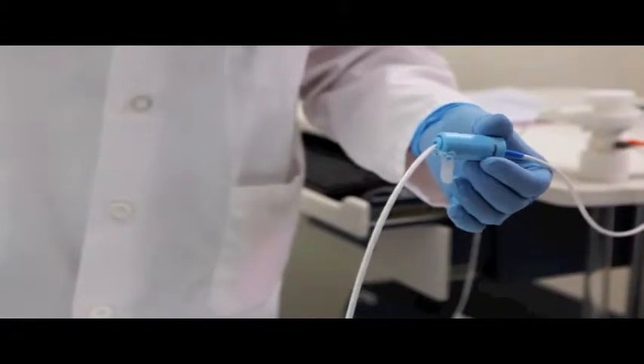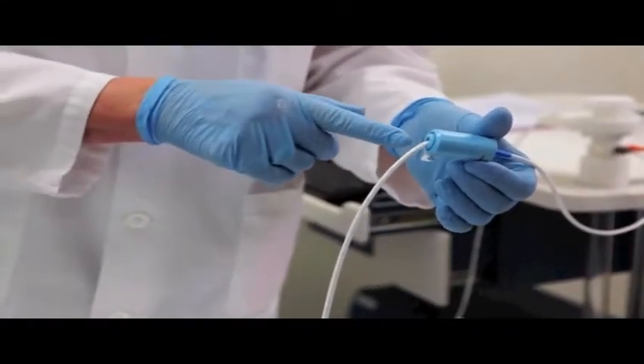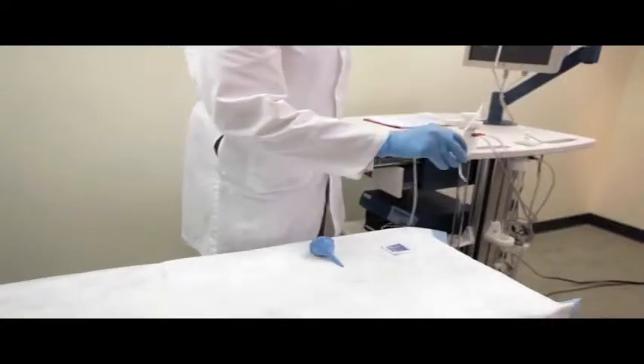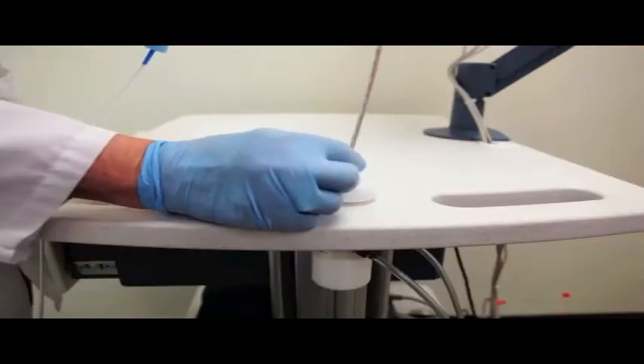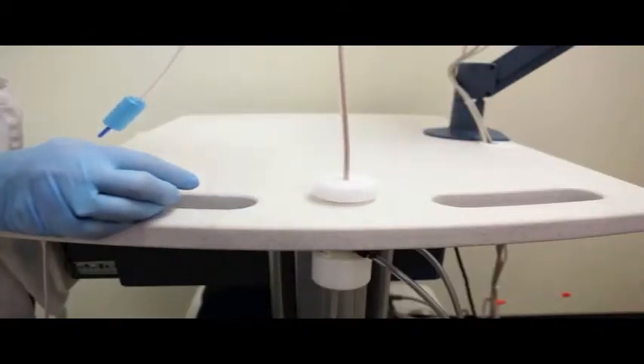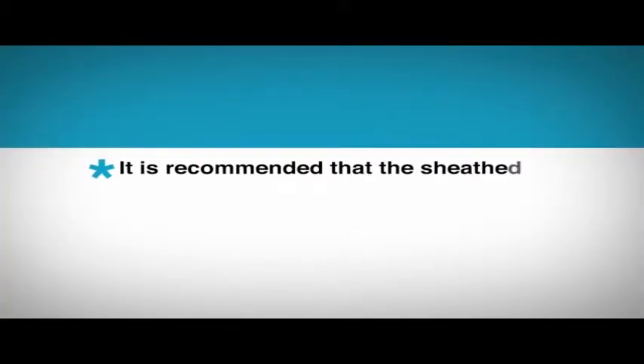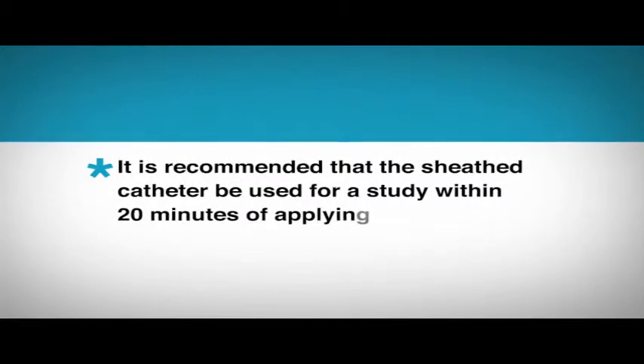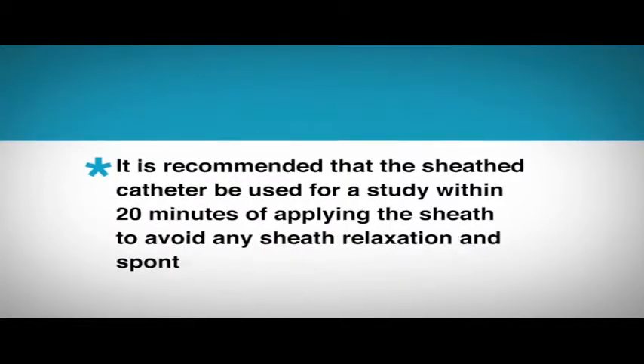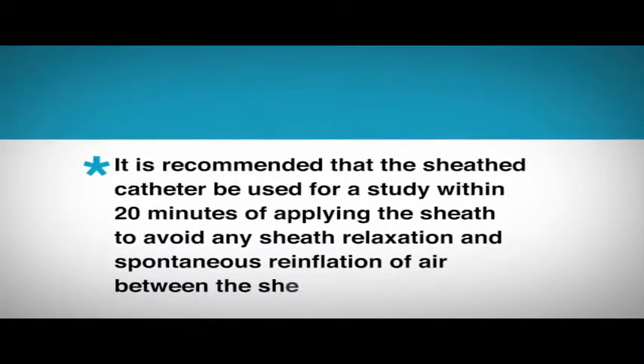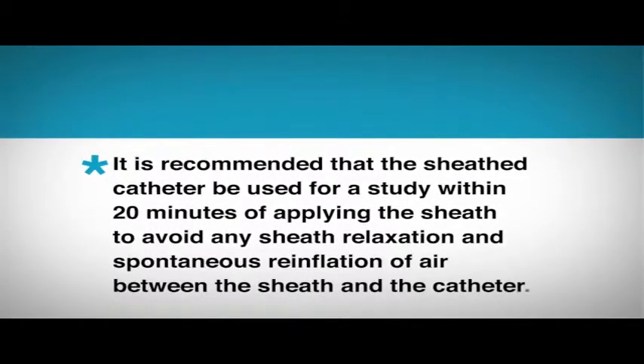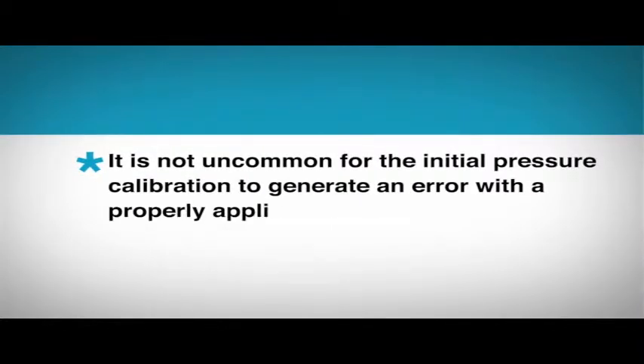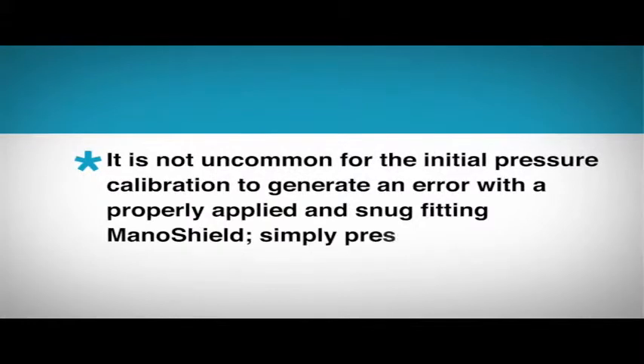If the tab is not secured against the base of the slider, it may cause the catheter to bend. You are now ready to pressure calibrate the catheter and then intubate the patient and perform the procedure. It is recommended the sheathed catheter be used for a study within 20 minutes of applying the sheath to avoid any sheath relaxation and spontaneous reinflation of air between the sheath and the catheter. It is not uncommon for the initial pressure calibration to generate an error with a properly applied and snug-fitting Manoshield.